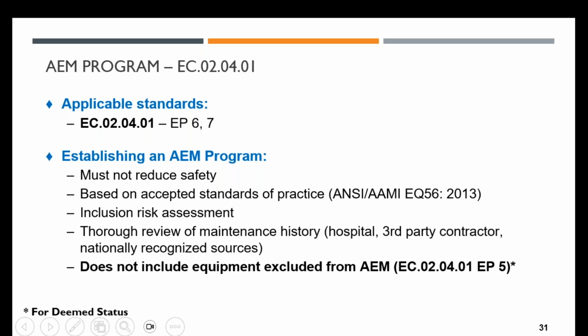So if you do want to establish an AEM and not follow manufacturer's guidelines, there's certain criteria that you should follow or consider. First, the AEM must not reduce the safety of the device, and it should be based on accepted standards of practice, like the ANSI/AAMI EQ56:2013 Recommended Practice for Medical Equipment Management Program. But you also have to do an inclusion risk assessment for determining what equipment goes in your AEM. You also have to review a thorough maintenance history, from your own hospital experience, or maybe a third party contractor or nationally recognized sources like AAMI.